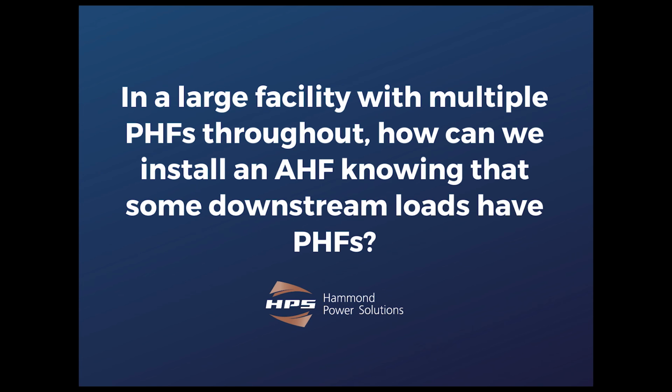It's not something I touched on in the presentation, but there is something called hybrid solutions. It may be sensible sometimes to do a combination of passive harmonic filters and active harmonic filters.